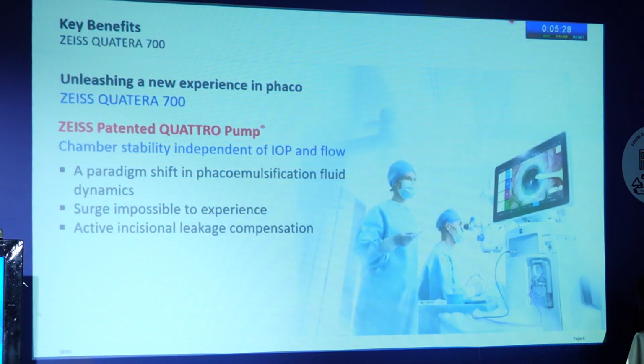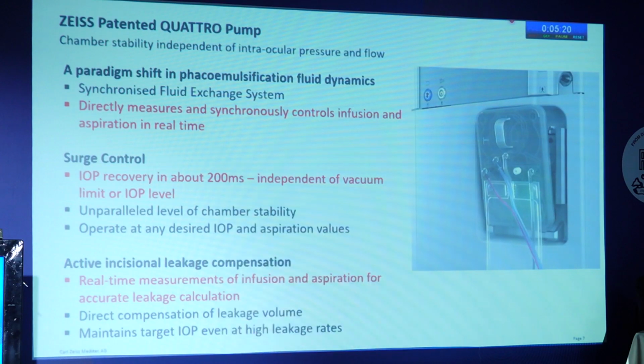Most interesting is this Quattro pump, which is patented, and the mechanism is completely different from almost all other fluid dynamics that are available. There is a synchronized fluid exchange system, and it directly measures and synchronously controls infusion and aspiration in real time. The surge control is excellent. IOP recovers in 200 milliseconds, and it is not dependent on the vacuum limit or the IOP level, which is set. It has a facility to measure the infusion and aspiration volume in real time, and therefore it can calculate the leakage from the incision, and it can compensate for that leakage.